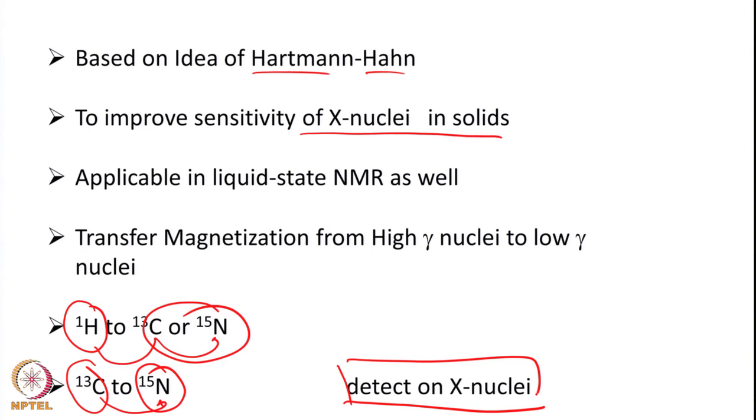Why do we detect on X nuclei in solids? Because dipolar coupling — where two spins are connected through space — is huge in solids, and for proton the dipolar coupling is very, very large. This leads to severe line broadening, so in solids X nuclei are generally detected. Since X nuclei are detected, it is imperative to enhance their signal by transferring polarization from more sensitive nuclei such as protons to less sensitive ones such as carbon or nitrogen.